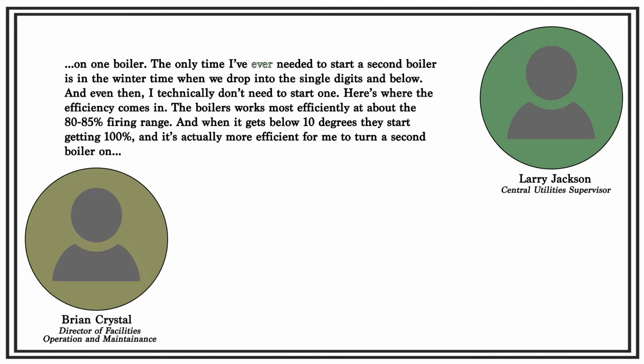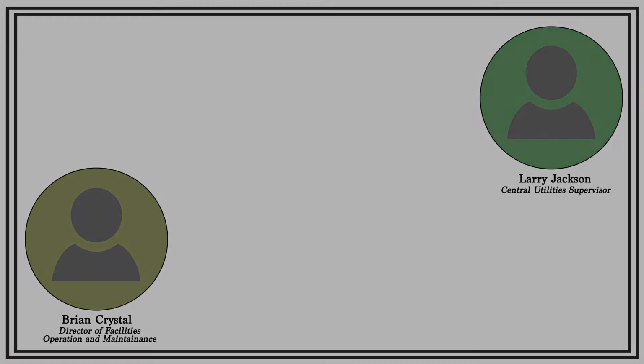We can do it on 1? The only time I've ever needed to start a second boiler is in the wintertime when I drop into the single digits and below. And even then, technically, I don't need to start one. Here's where the efficiency comes in. The boilers work most efficiently at about the 80 to 85% firing range. And when it gets below 10 degrees, they start hitting 100%. It's actually more efficient for me to turn the second boiler on at a low rate.